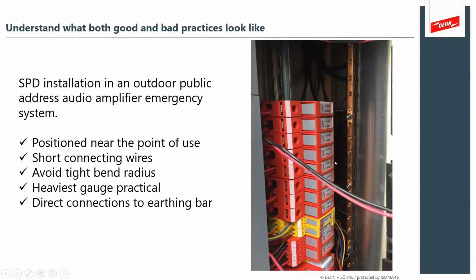So what are we looking for? It should be positioned near the point of use, where it will make a difference and control the voltage at the amplifier. You want to use short connection wires. You want to avoid tight bend radius. You want to use the heaviest gauge possible. You want to direct connect to the earthing bar, which you can see we've easily and effectively set up with this surge protection arrangement. In this case, it has protection for the DC output of the red and the black, but it also has protection of the rest of the CAN bus and IO control within a cabinet like this.